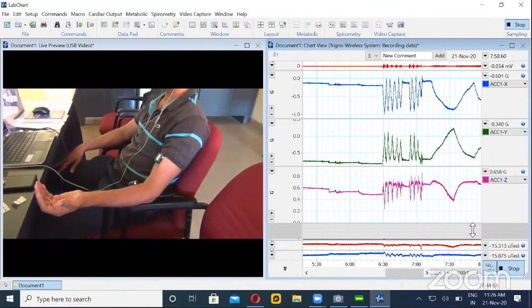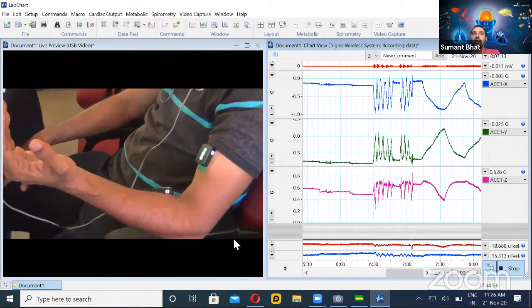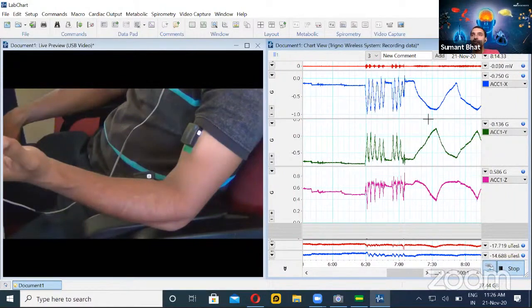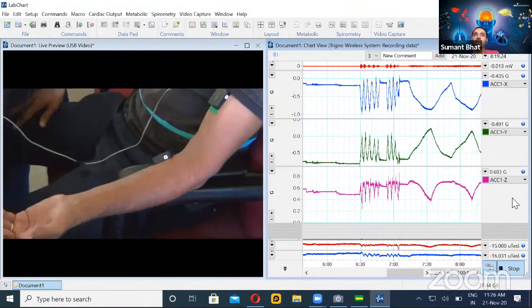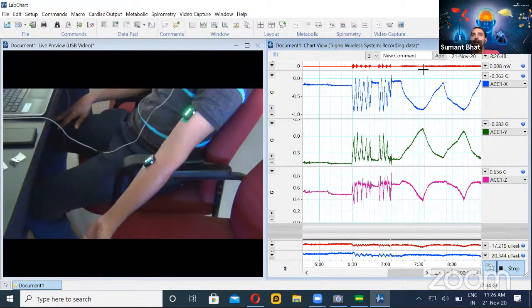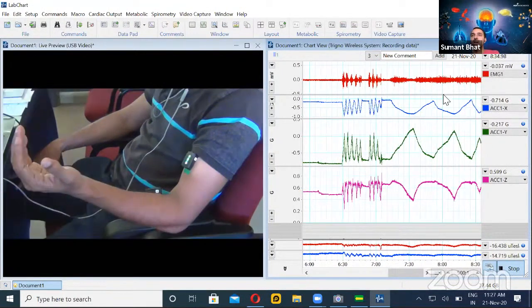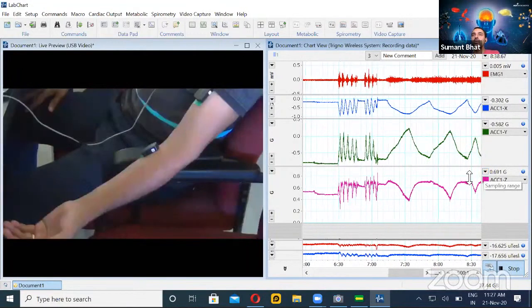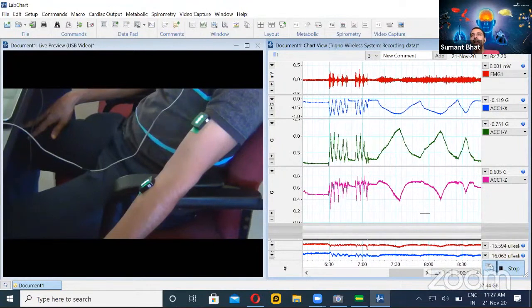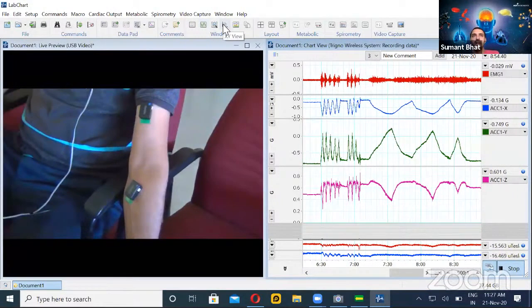The accelerometer is built into the Delsys sensor. Each sensor comes with almost nine degrees of freedom signals — three accelerometers are part of it. This can be useful for movement analysis: if you want to see whether there is EMG or if there is a tremor or only vibrations, you can pick up those vibrations from the accelerometer data. You can also use it to look at stability.